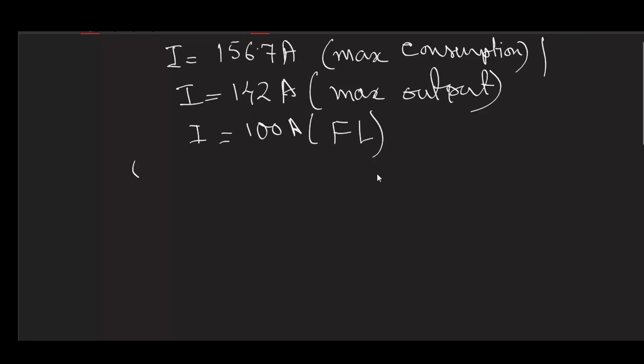And what are the corresponding power factors? Here if we calculate, we will get 0.79. Here we will get 0.86. Here we will get 0.97. So gradually, as we increase the loading, the machine delta has increased. We are putting so heavy a load on the machine shaft that the machine tries to find some kind of relief, and that is why it has no choice other than increasing the delta value.